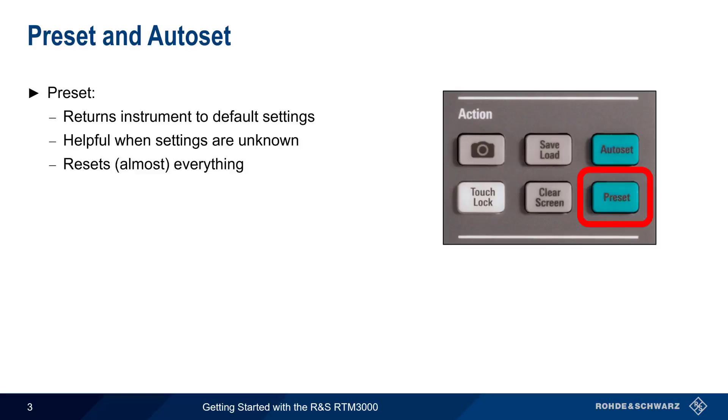Before we begin configuring our scope and making measurements, there are two very important front panel keys that you need to be familiar with: Preset and Autoset. Preset is used to return the scope to its default settings. This is very helpful if you're unsure about what the current settings are. Although Preset resets almost all the settings, it doesn't erase any data you've stored on the instrument.